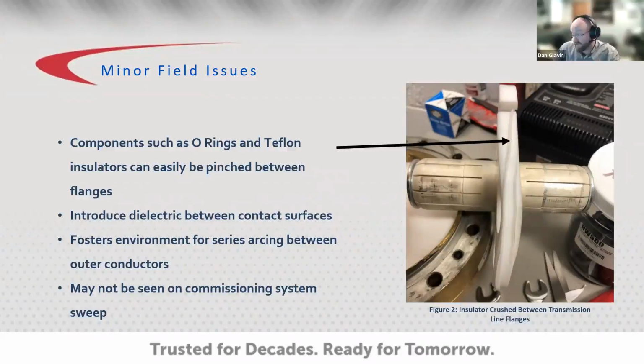This pinched material introduces an undesired dielectric constant between outer conductors, therefore intensifying the electric field and breakdown voltage at this particular location. Depending upon the magnitude of the mismatch and the location, this issue may not be diagnosed during a system time domain reflectometry measurement or the system's commissioning.